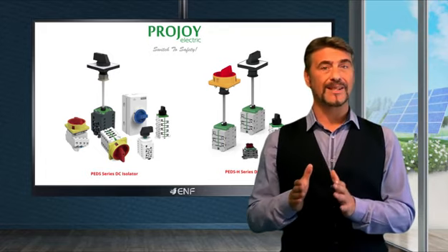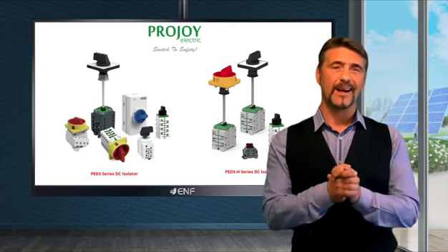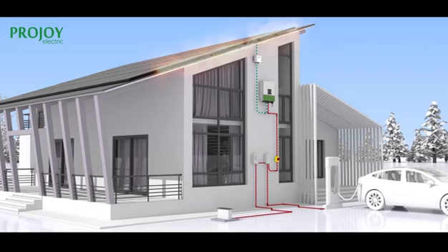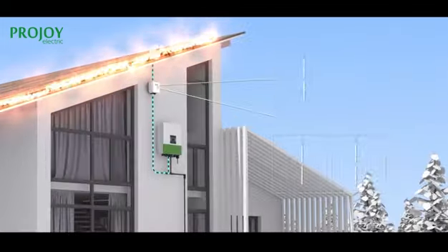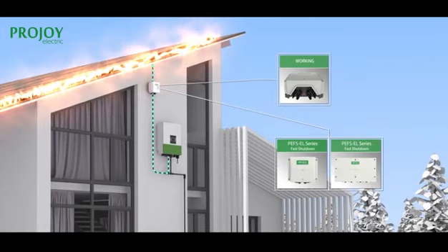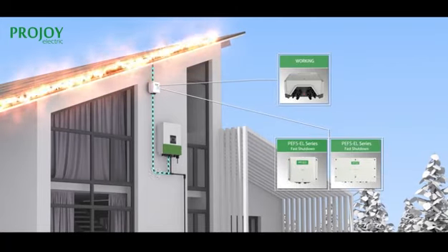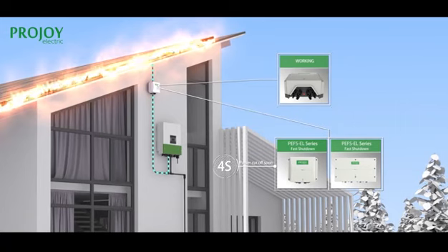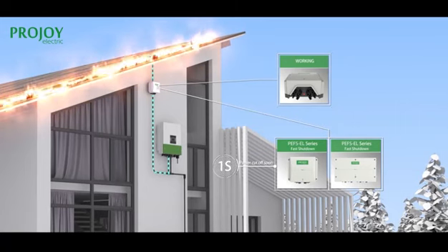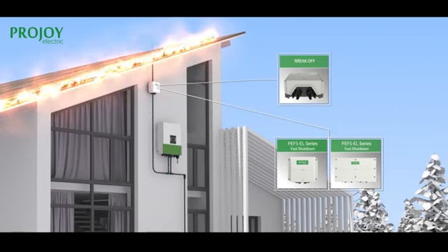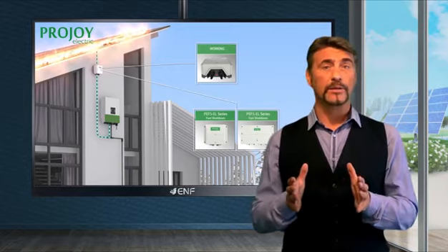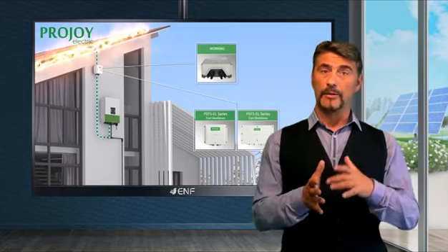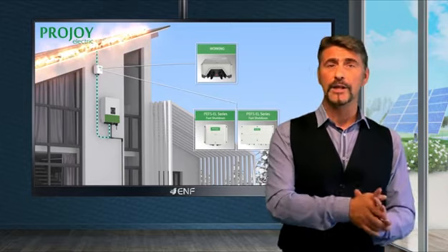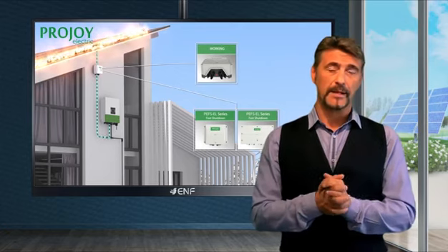In general, DC isolators are employed in a solar array to break the circuit current so that the individual solar modules and the inverter can be safely isolated for maintenance or repair. Even when the DC isolators are switched off, there will be a DC voltage generation of approximately 600 to 1500 volts between the module and inverter. If fire happens during the installation without the safety switch, the high voltage DC current inside the panel array, or between the panel array and the inverter, will threaten the safety of firefighters.